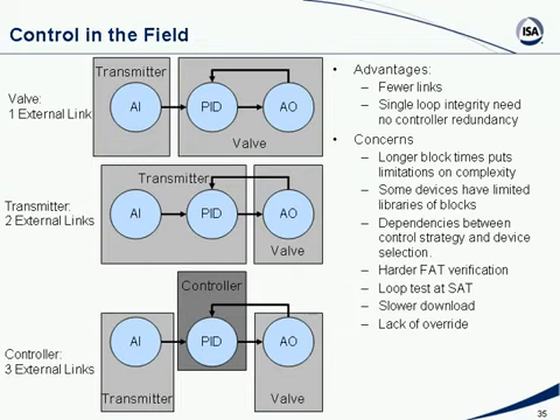If I put the PID in the transmitter, as you can see from the second diagram, I get two values communicated across the fieldbus: the output of the PID and the actual valve position feedback. If I put the PID in a centralized controller, which is completely possible and a lot of people do it, then I need to communicate three links across the fieldbus: PV from the transmitter to the controller, output from the controller to the valve, and the actual valve position from the valve to the controller. Each communication link takes 30 milliseconds, so you will find that doing control in the controller is in fact slower than doing control in the field.